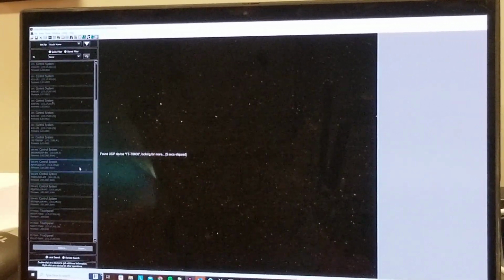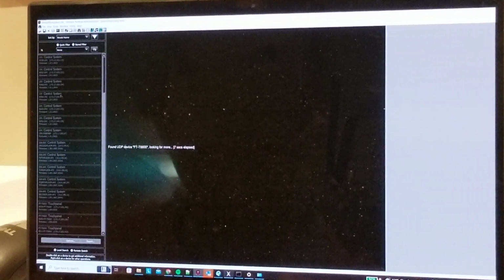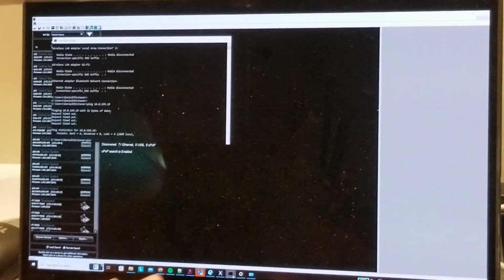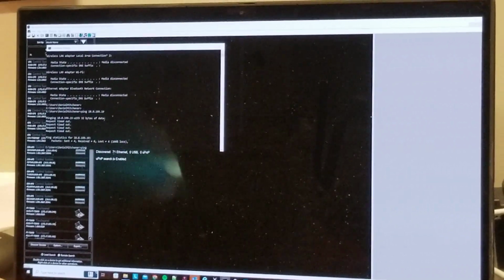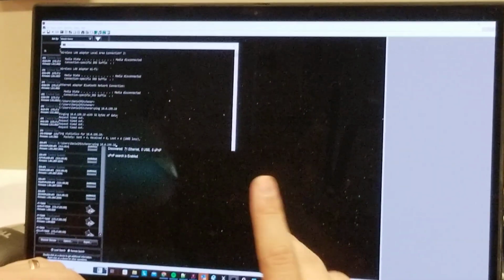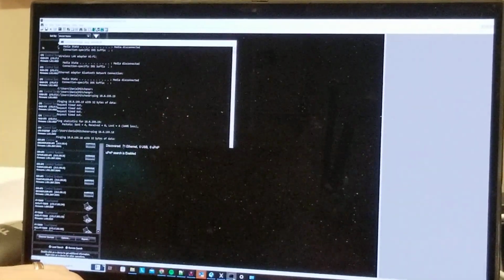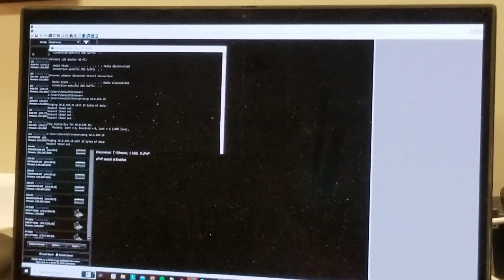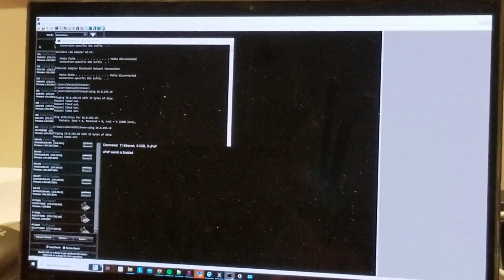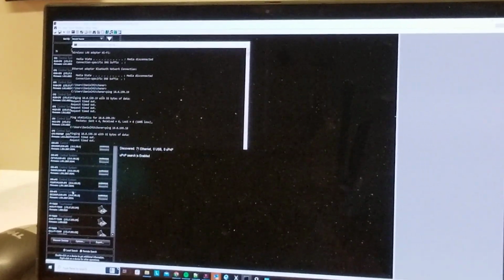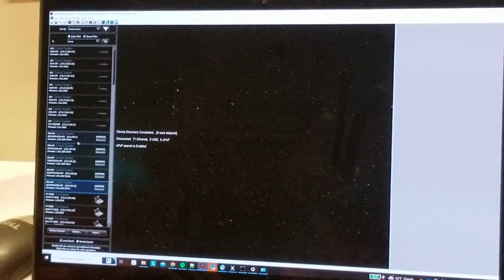So even though it's saying it sees everything here, for whatever reason, it can't actually talk with any of the parts over the Ethernet. And then I'm going to try just pinging the DALI that's right here. And yeah, same deal. Just throwing it out there, is there ever a time where you have to do a hard reset of everything, like a computer, where eventually you got to power it down and power it back up?